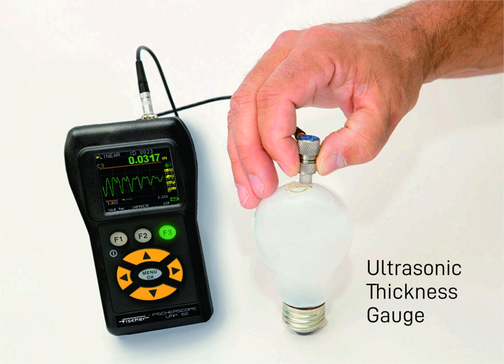An ultrasonic thickness gauge is a measuring instrument for the non-destructive investigation of a material's thickness using ultrasonic waves. The usage of an ultrasonic thickness gauge for non-destructive testing to check material properties such as thickness measurement is now regularly utilized in all areas of industrial measurements. The ability to gauge thickness measurement without requiring access to both sides of the test piece offers this technology a multitude of possible applications, especially in pipes.